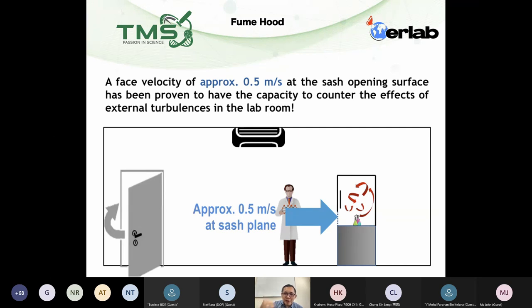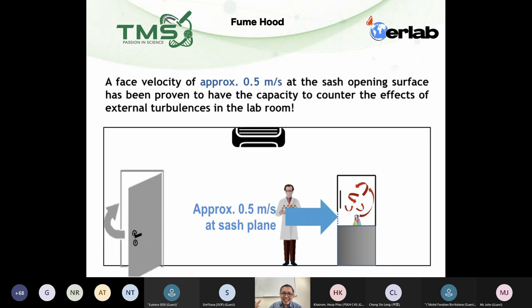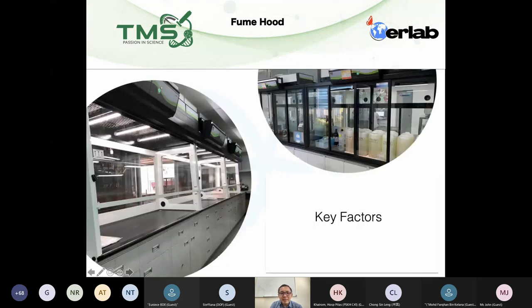One thing to remind your colleagues: never place a standing fan blowing toward the sash opening. I have seen some labs do this because the lab is very warm, but doing so means you cannot reach 0.5 meters per second face velocity.